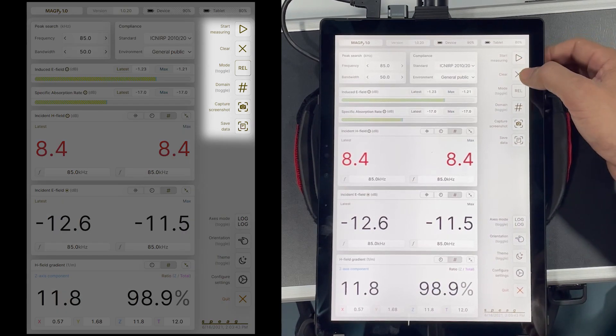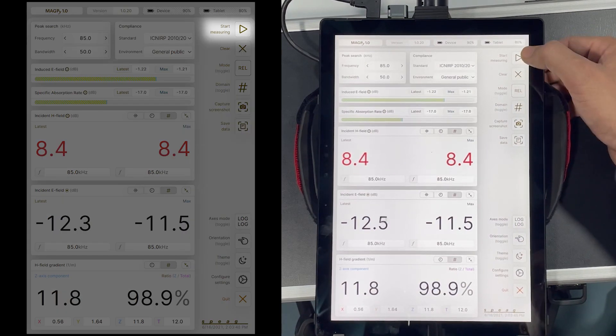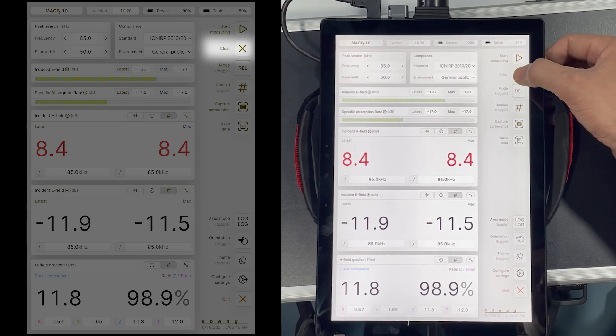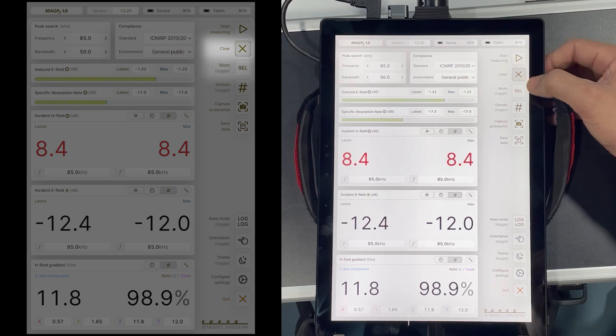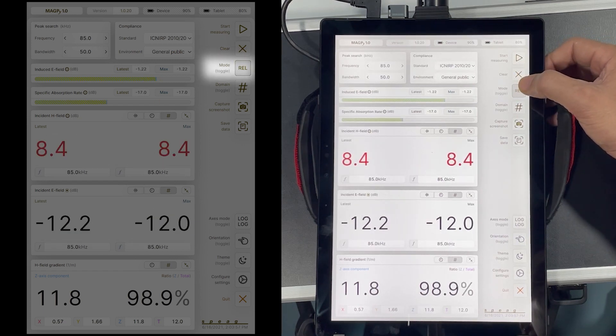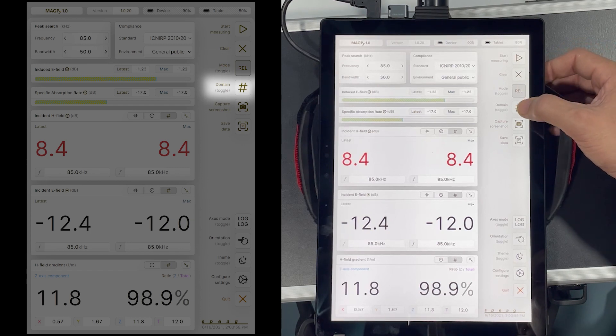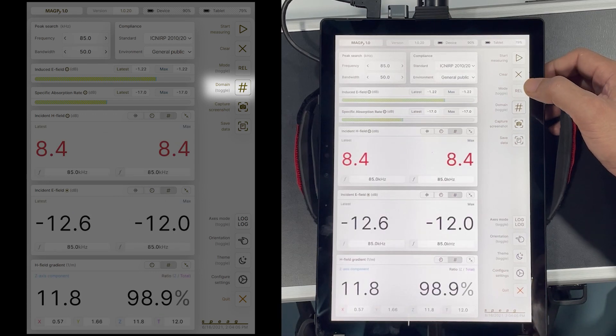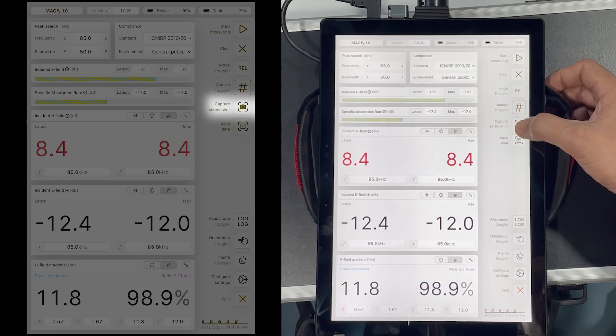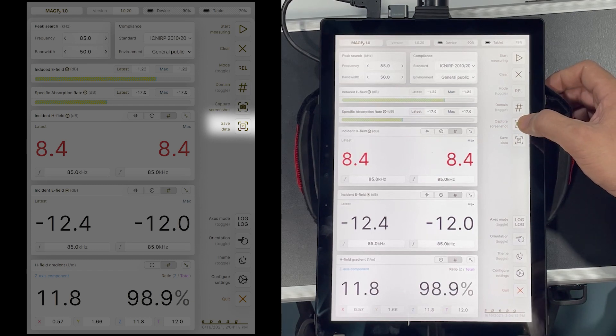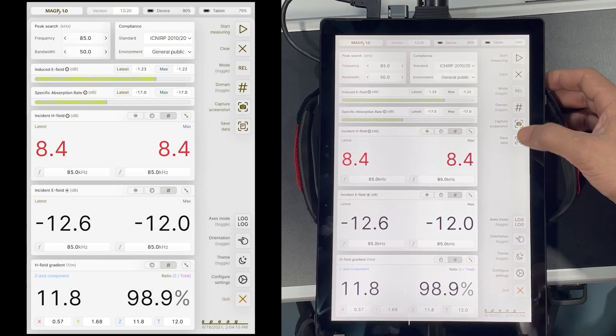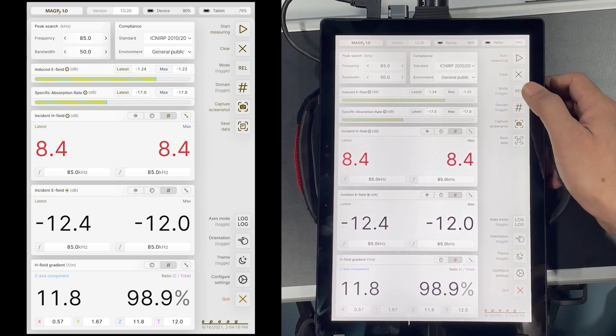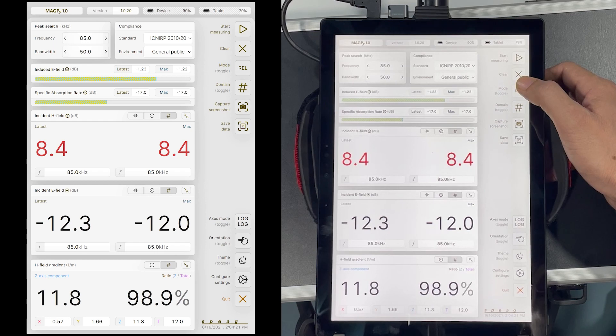In this case, the buttons on the right allow the user to start or stop a measurement, clear the max hold values for a fresh evaluation, toggle between absolute and relative values, switch the induced field windows from frequency or time domain to numerical modes, save a screenshot or measurement data to the connected USB drive as well as the MAGPy device. These buttons are easily operated with the thumb.